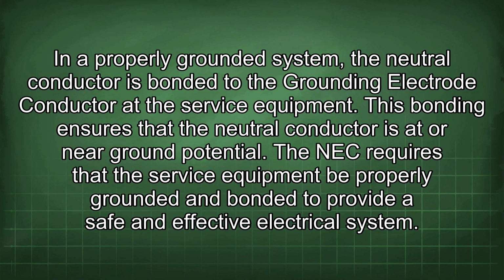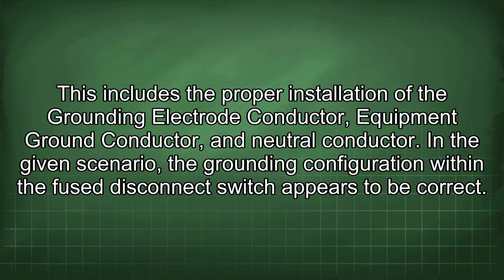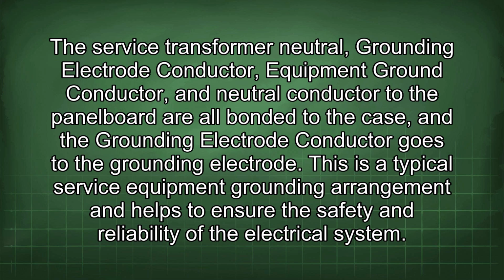The NEC requires that the service equipment be properly grounded and bonded to provide a safe and effective electrical system. This includes the proper installation of the grounding electrode conductor, equipment ground conductor, and neutral conductor. In the given scenario, the grounding configuration within the fuse disconnect switch appears to be correct. The service transformer neutral, grounding electrode conductor, equipment ground conductor, and neutral conductor to the panel board are all bonded to the case, and the grounding electrode conductor goes to the grounding electrode. This is a typical service equipment grounding arrangement and helps to ensure the safety and reliability of the electrical system.